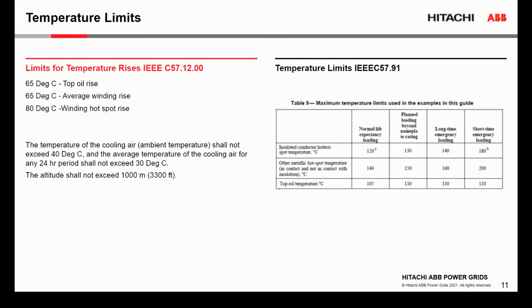And the temperature limits for the temperature rises may change if we see that the ambient temperature is higher, or if the elevation of where the transformer is installed is higher than 3,300 feet. So the absolute temperature limit for the hotspot in the windings is limited to 130 degrees C. This is with the assumption that the transformer has thermally upgraded insulation paper. And top oil for the normal loading is limited to 105 degrees C.